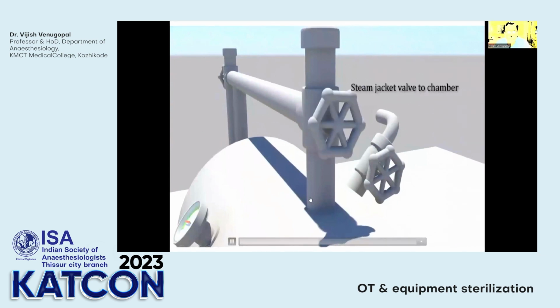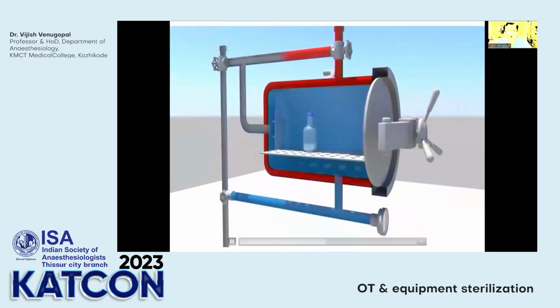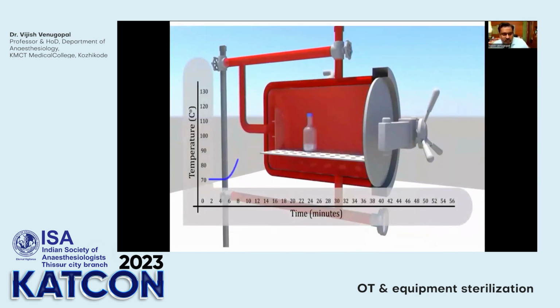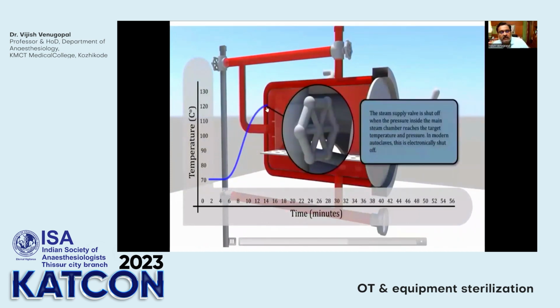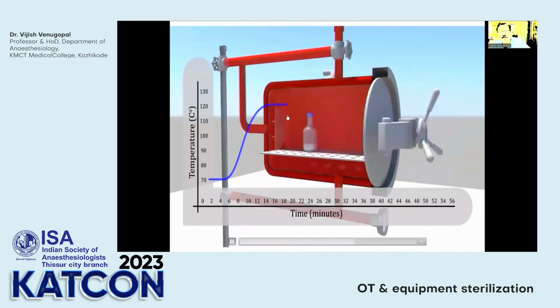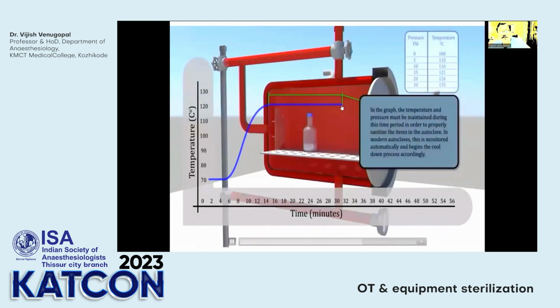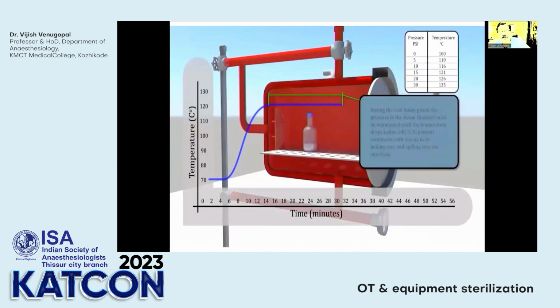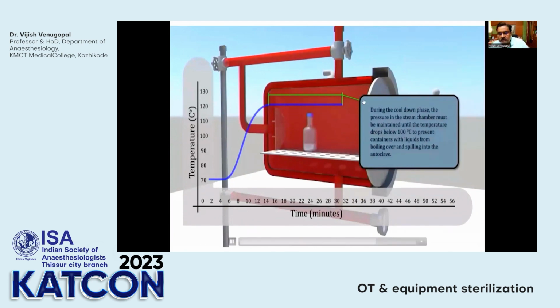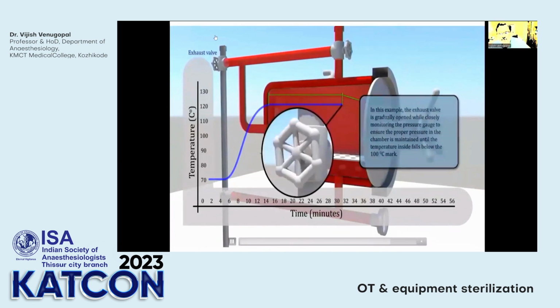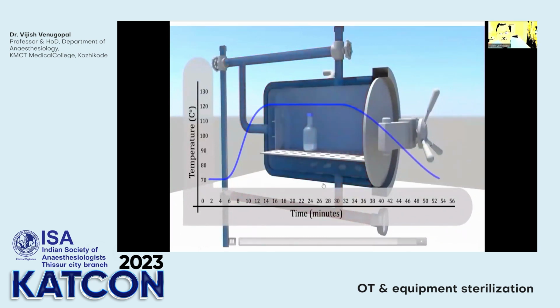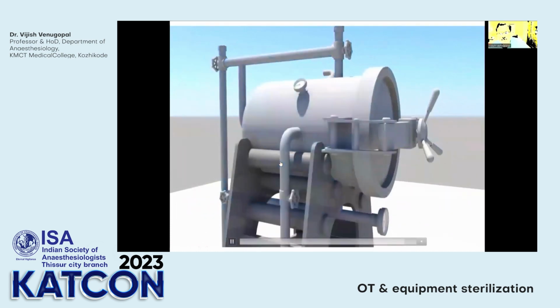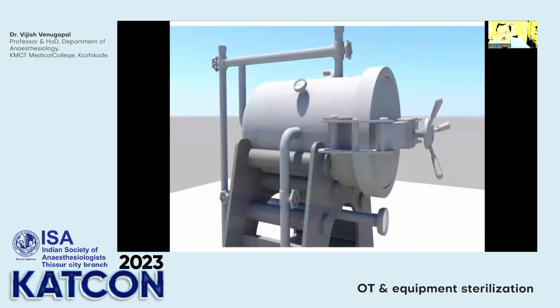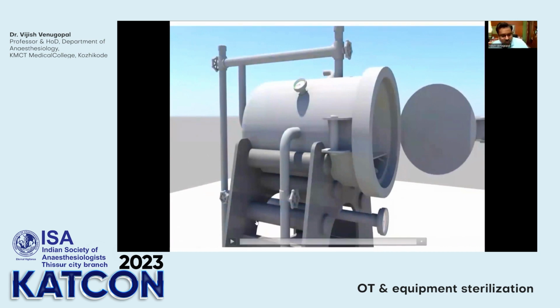And later, this steam jacket valve gets opened, and through this tube, it then goes into the steam chamber. So initially, a vacuum is applied to remove the atmosphere from the chamber, and then later the steam supply valve is shut off when pressure inside the main steam chamber becomes appropriate. So the temperature and the pressure must be maintained during this period in order to properly autoclave. And at the end of the time duration, what happens? You get into the cool down phase. In the cool down phase, this exhaust valve is slowly opened and the steam is removed. So this is how the autoclave works, and this is all now automated. And if the temperature is increased, you can reduce the time for the autoclaving. Okay, so this was just an animation.